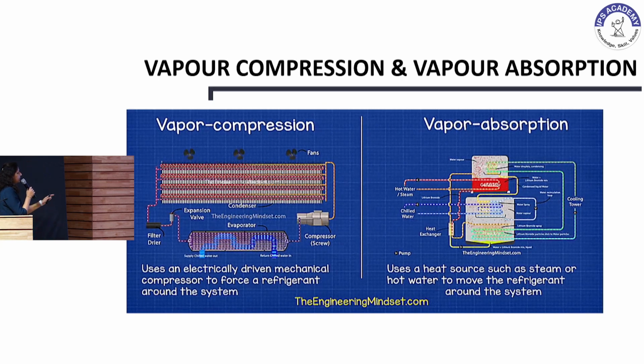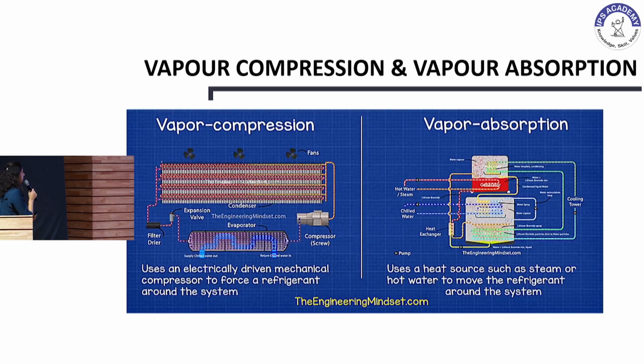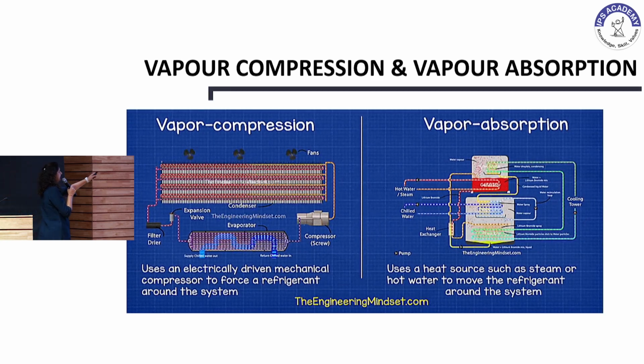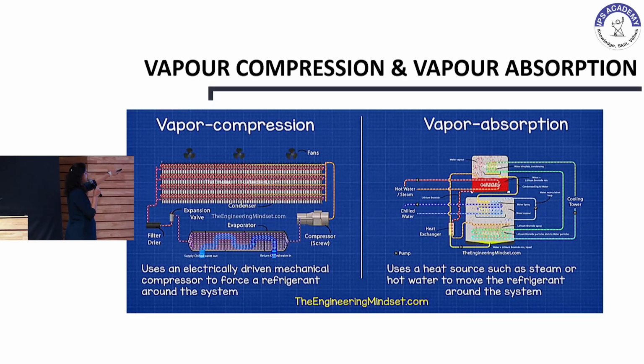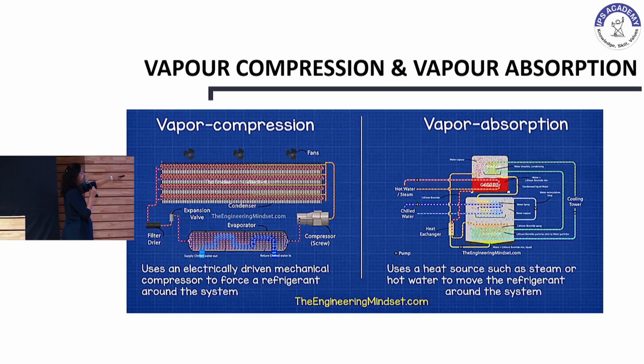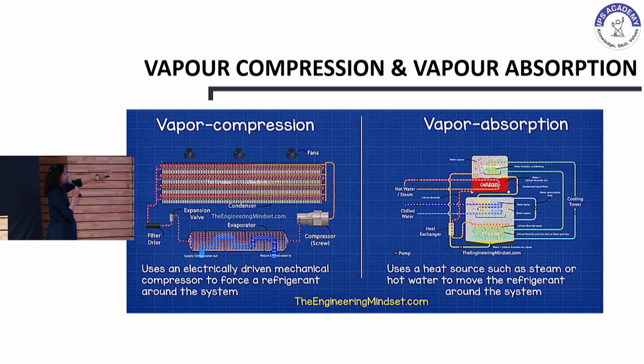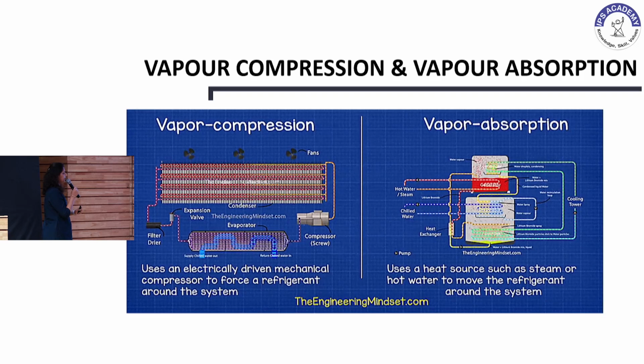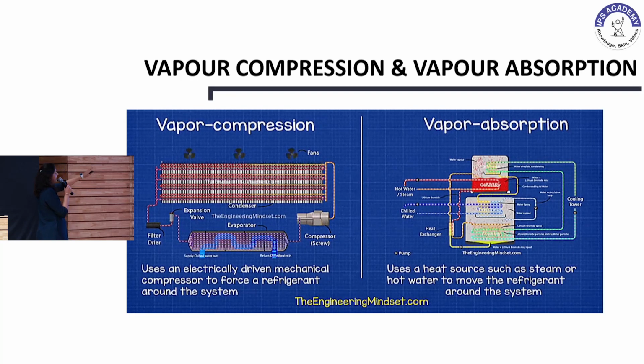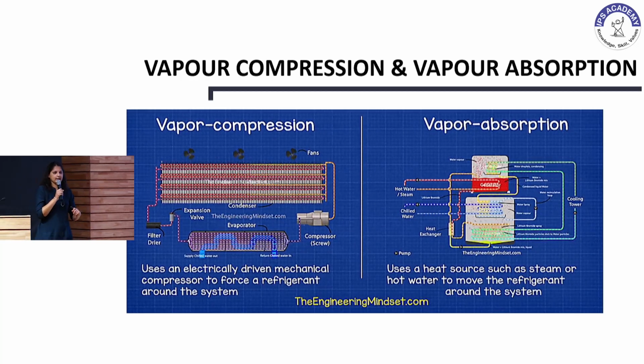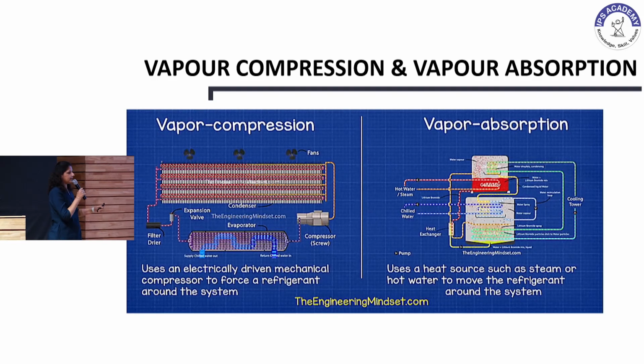So these are two images which you can see, of vapor compression and vapor absorption. Here you see the condenser condensing the vapor, which goes through the filter dryer and expansion valve to the evaporator. From the evaporator, it is evaporated, and the evaporated gas goes to the compressor to get compressed, and then it again goes to the condenser. Now these condensers can be of two types: shell and tube, or coil types, which we will also learn in the upcoming slides.